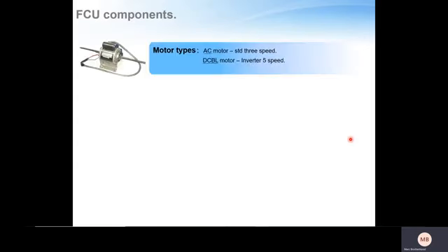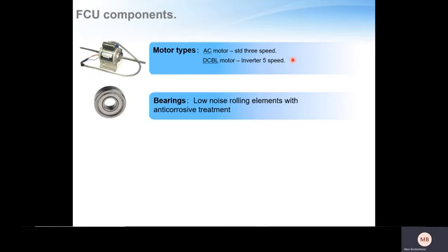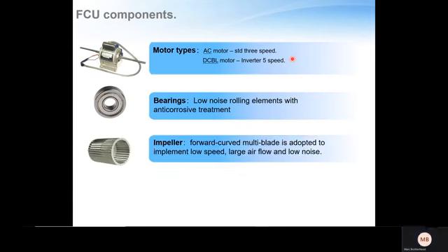We have a look at some of the unique fan coil components. The motor types, we only have one model that comes with a permanent magnet inverter motor. The rest are AC, your conventional induction motors, they come in standard 3-speed, and the inverter motor has up to 5 different fan speed settings on it. The bearings have been relooked at, and the factory are using low noise rolling elements, and they've also put anti-corrosive treatments within the rolling elements in the ball races. The impellers have been made of metal. They're forward curved multi-blade, adopted to implement low fan speed with the advantage of large airflow and generating low noise, hence the big squirrel cage motors.